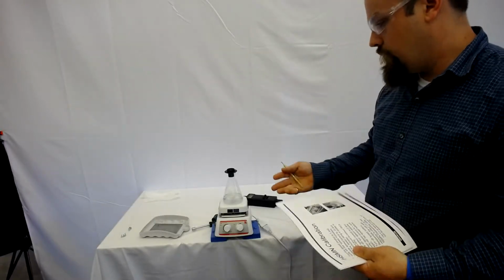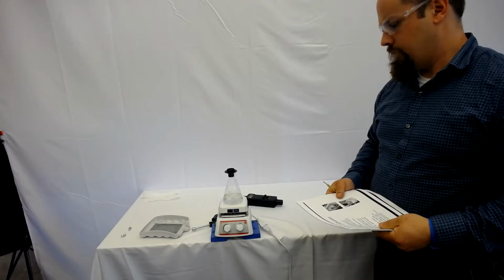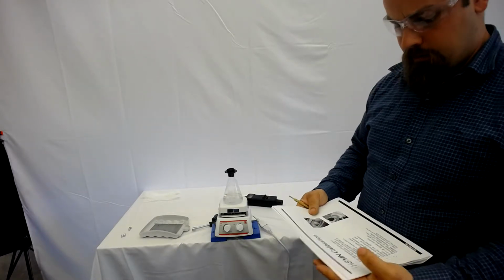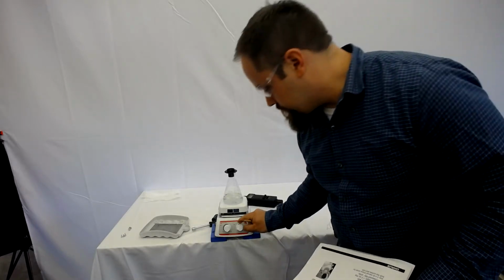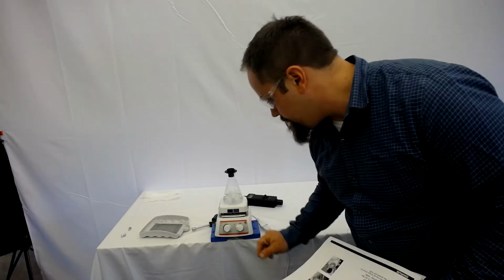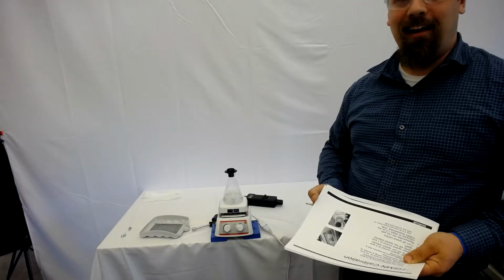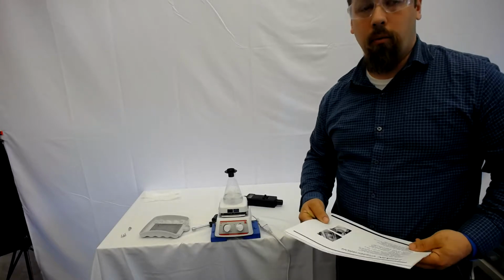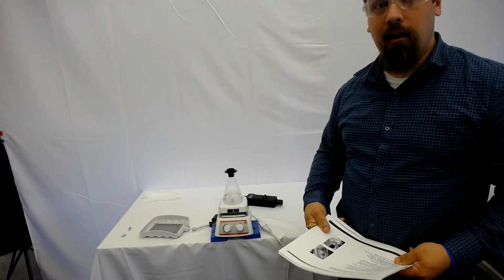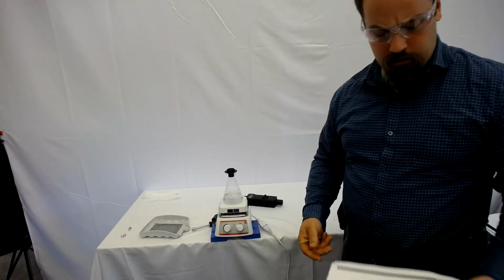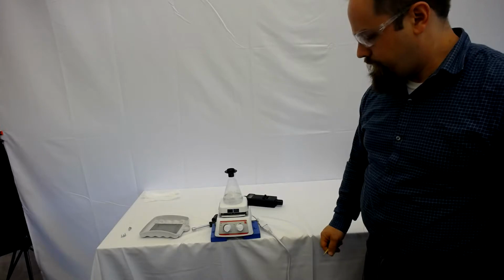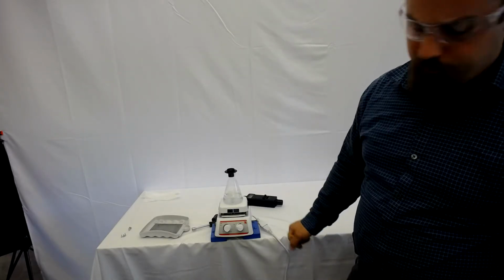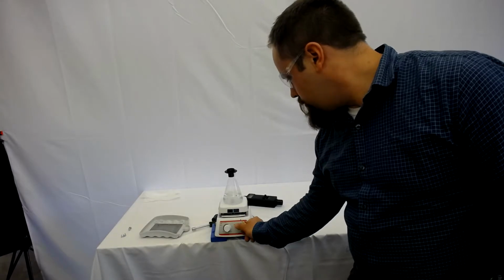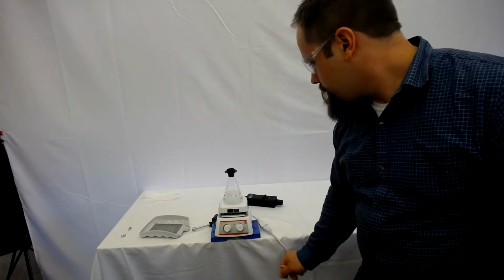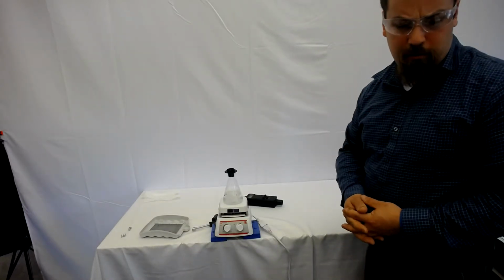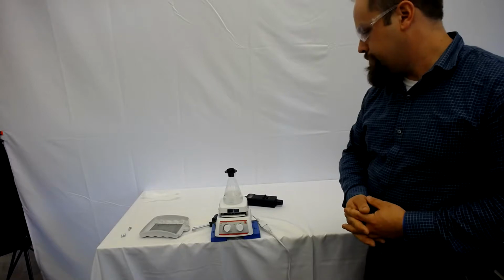All right, we're going to let that go, make sure that it does not stop. And we're going to turn the speed control up to position 5. What we're looking for here, we're not looking to get a specific value. We are looking to make sure that the speed does indeed increase as we move to position 5. All right, then we're going to move it up to position 10. What we're looking for here is to make sure that the unit does not decouple.